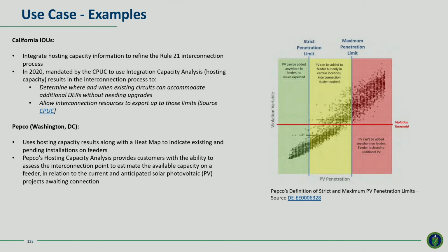One example is from a utility in DC, where there's an area a feeder can accommodate a certain amount regardless of location. Beyond that, additional capacity depends on location, if it's close to the substation or close to the load. Beyond a certain line, it doesn't matter where you put it, you're going to see issues. This is a stochastic analysis since it could be located in different places, but knowing how much you can get on a feeder, up to a limit, helps design a better screening process.